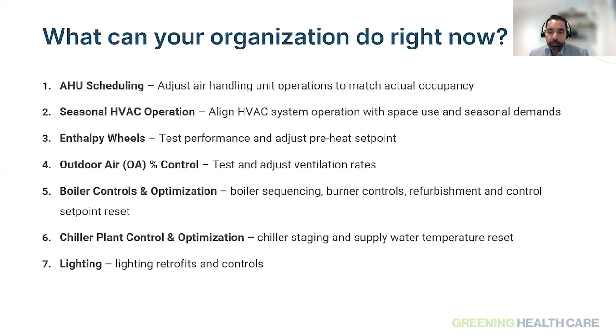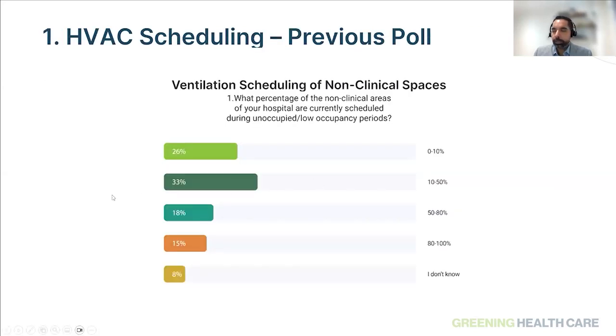in greening healthcare facilities. We'll review outside air control as well. That adds to the amount of outside air you bring into the facility, and if it's not optimized, it ends up being a higher heating load on your building. Boiler control optimization, staging of the boilers, and similarly staging of the chillers tied to the building automation system is an easy measure that should be applied across all the facilities. And then we look at the lighting, what you could do with your existing lighting control systems. Feel free to jump in with questions, and we'll tackle them as we go through.